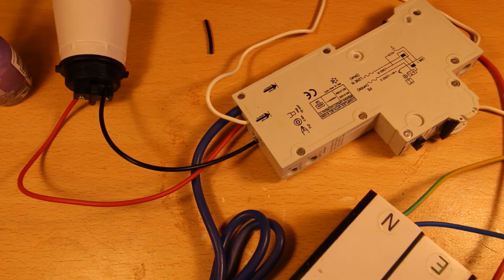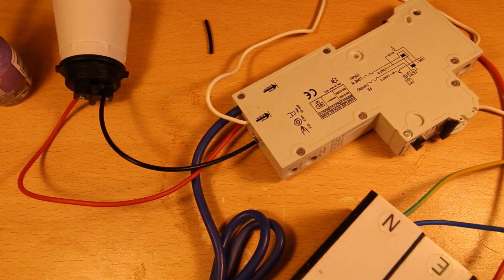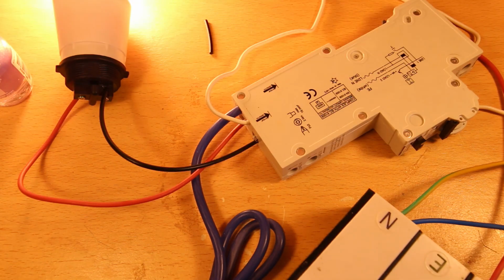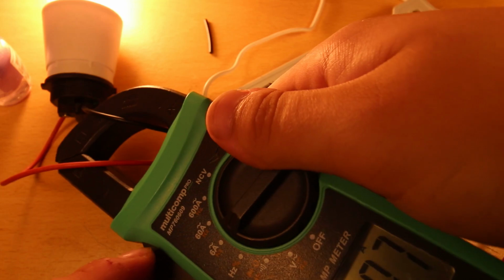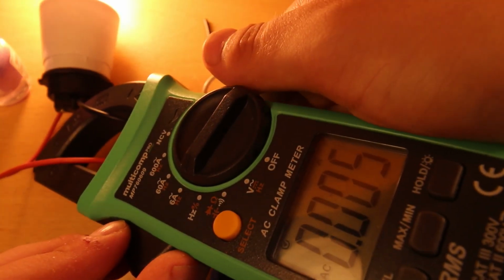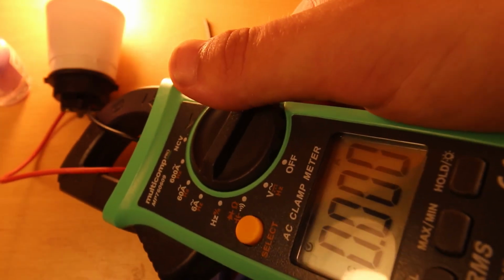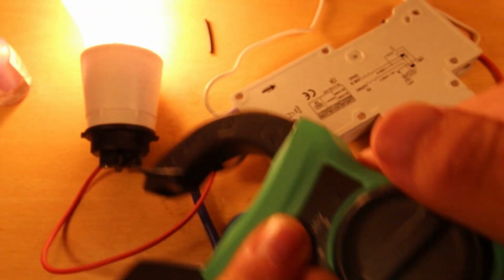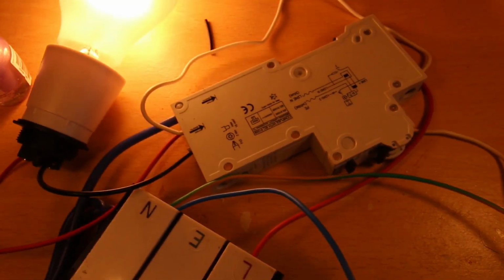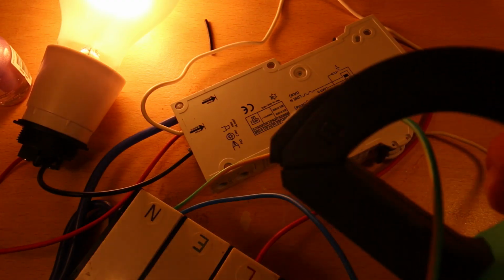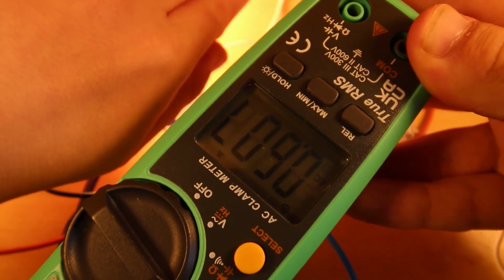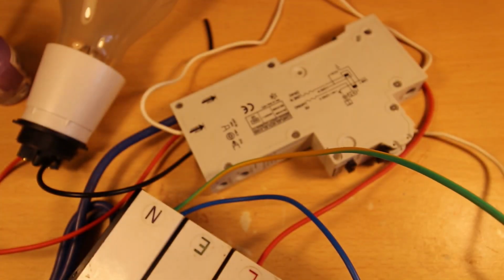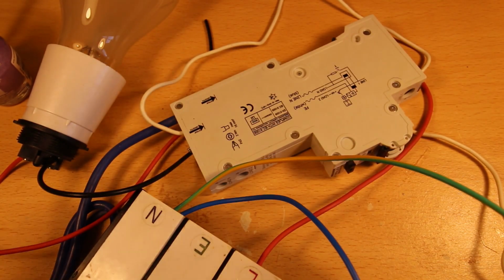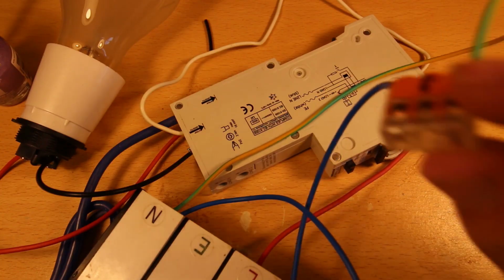If I then disconnect the pen from the main earth again, so here it is, disconnected, and I power this back on and we put the current clamp back around, it is measuring 3 milliamps, 5 milliamps. It's still picking up noise from other things, but it measures no leakage, even though if I bring in my diverted neutral path and put that through, you can't make that out, so we'll cover this. 600 milliamps. There we go. So that proves it. Even with an RCD, it will not trip if the pen breaks, because there is no leakage. The leakage to earth happens in the head terminal here.